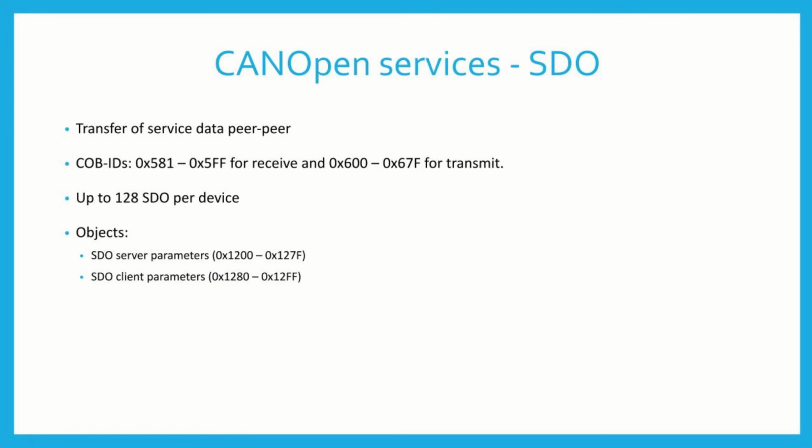A service data object is a service for transmitting long messages from one device to the other devices. The code IDs of these services are 600 hex plus node ID for receiving and 580 hex plus node ID for transmitting. SDO messages are permitted in the initial or stop state. The communication is always initiated by the SDO client.